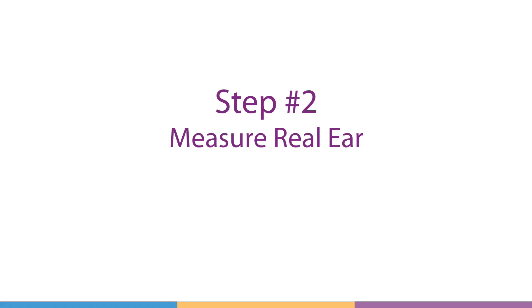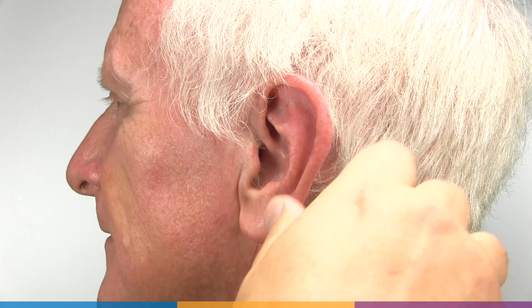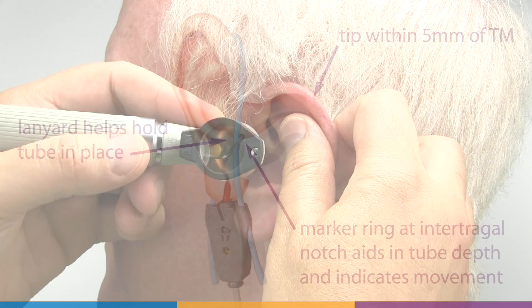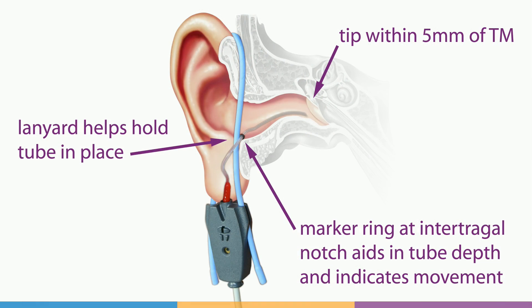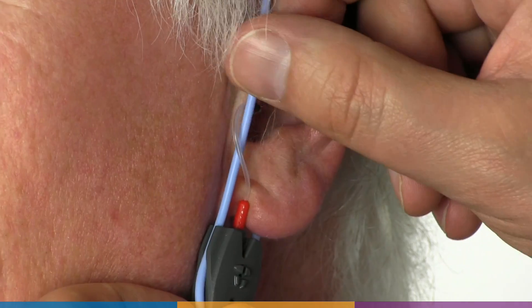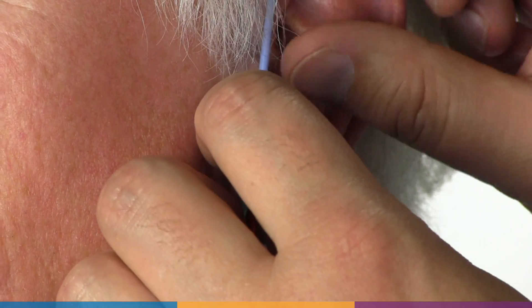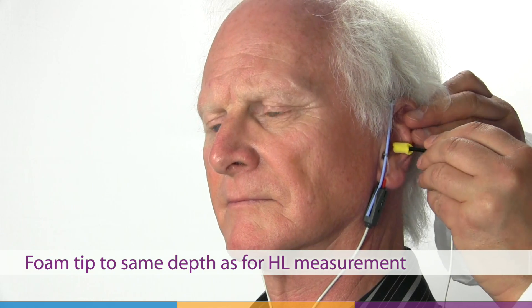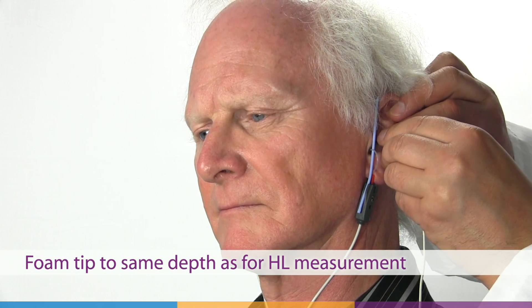The RECD measurement on the ear is made using a probe microphone. As with all real ear measurements, the ear canal is first checked through otoscopic examination for obstructions and to ensure correct probe tube placement. Position the probe tube so that the tip is within 5 mm of the tympanic membrane. Connect a foam ear tip to the RECD transducer and, without moving the probe tube, carefully insert to the standard depth and ensure enough time passes for the foam to fully expand.